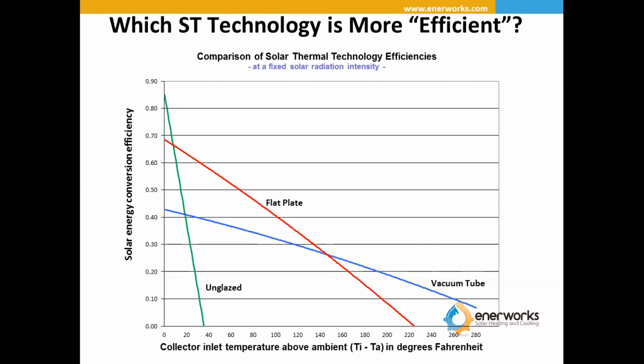So if you look at the inlet temperature versus the ambient temperature, typically pool collectors would be very low because you're not trying to heat it up to anything, say, above 85, 86 degrees. Your ambient temperature is often, in some cases, warmer than that. But as your ambient temperature gets further and further away from the temperature being collected at the collector, you can see the efficiency drops pretty dramatically. So you would never be able to heat domestic water or space heating with an unglazed panel.